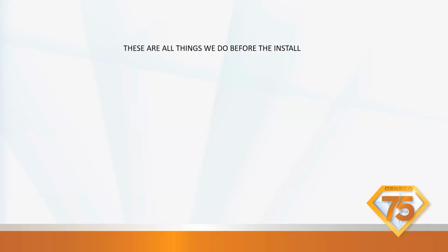Now, up here in North Idaho, what we do is we tell people when we install it that you're going to have to go out and shovel around it when it snows, okay? If we get a storm that's 3 or 4 feet deep, you're going to want to put it into emergency heat until you can get out there and shovel it out. You don't want to let it get covered with snow. Now, I know that we don't have those kind of storms all the time, but every once in a while we do. So you're going to want to remind your customers that they're responsible to go out and keep it clear.